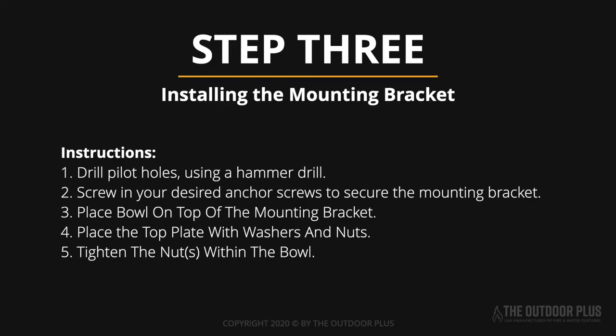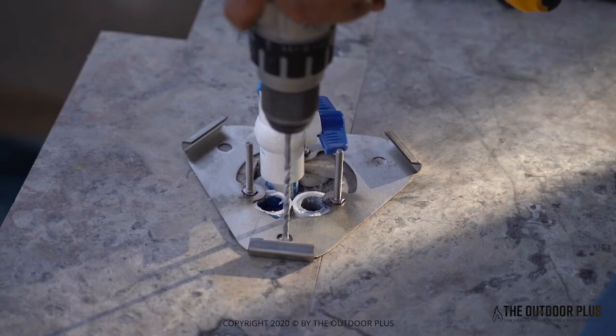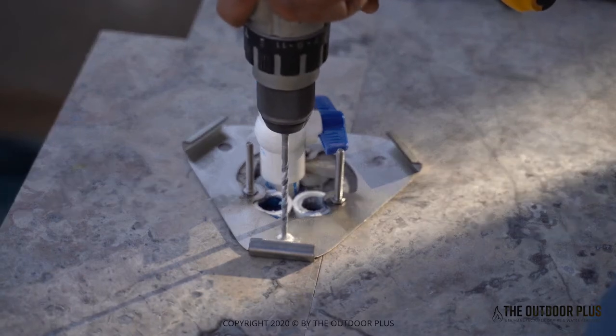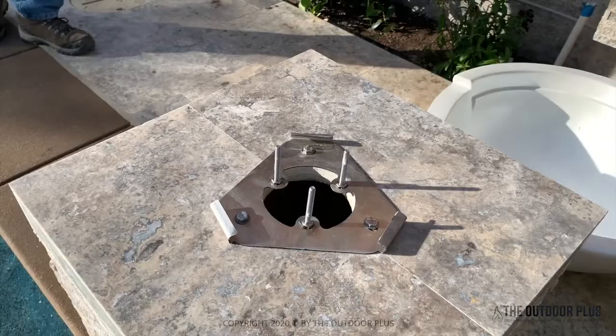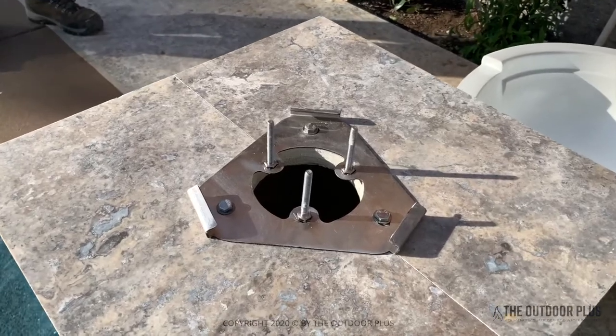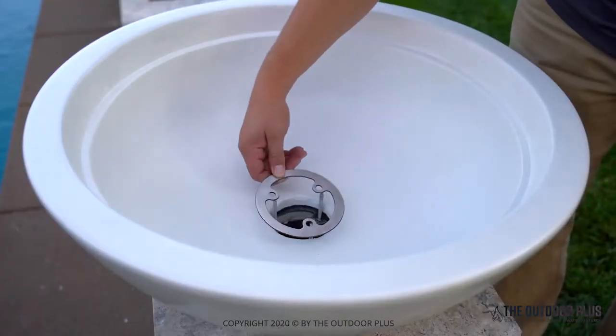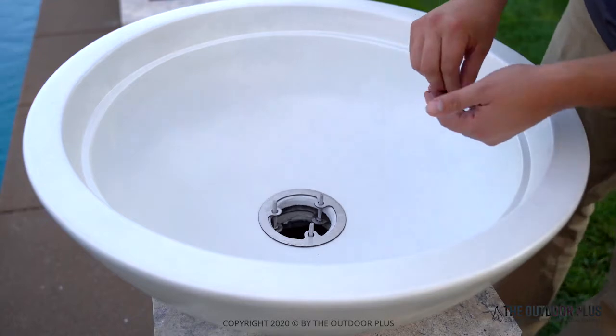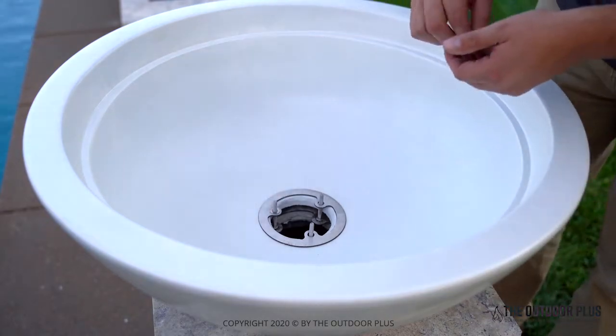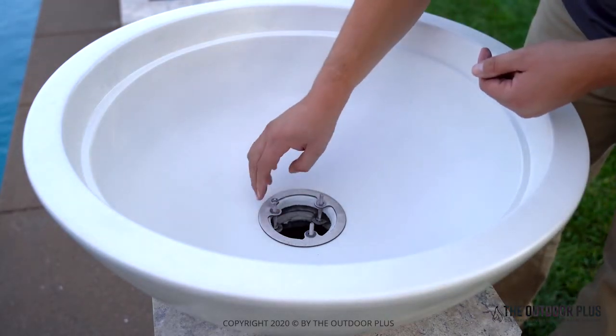Step 3. Mounting/vent bracket installation. The mounting/vent bracket is required for all fire bowl installations. Not using the mounting bracket will void the warranty. Use the mounting bracket as a template to drill pilot holes for the anchor screws. You may use your own preferred anchor screws for this installation. Place the bowl on the top of the mounting bracket and use the provided mounting plate and nuts to fasten the mounting bracket to the bowl.